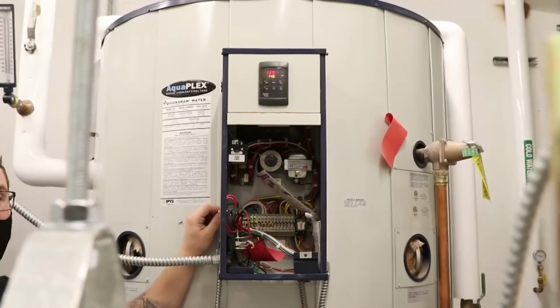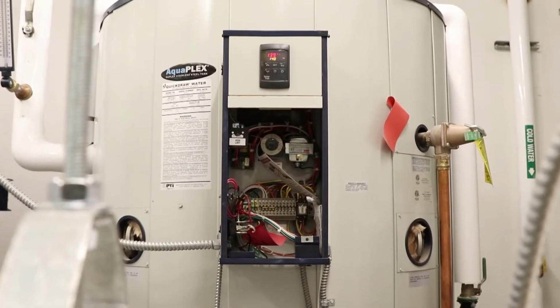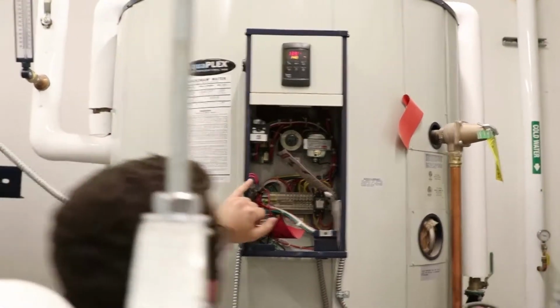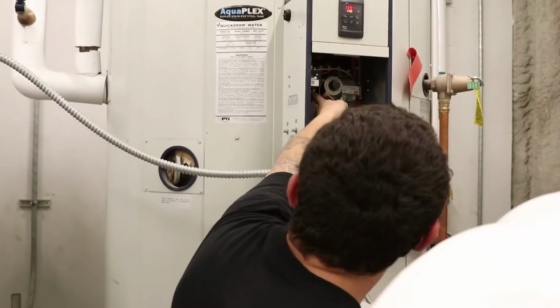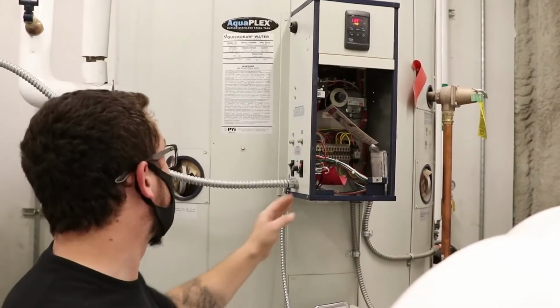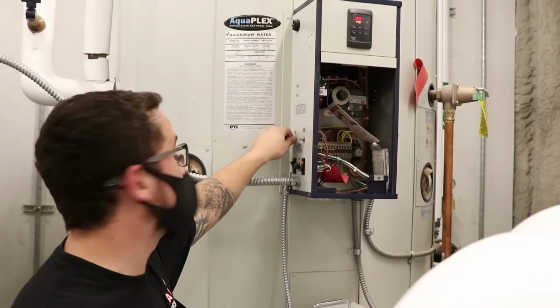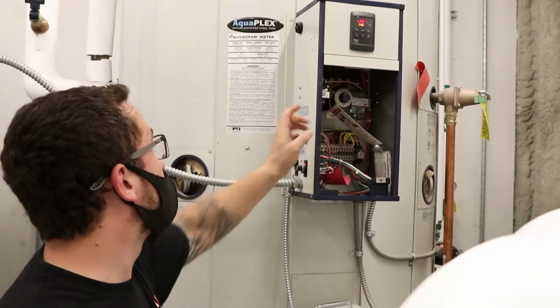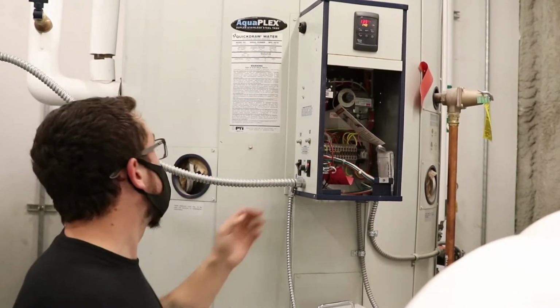As you can see, now you're in a low water condition where the water heater will not operate, to prevent a dry fire or damage to the heat exchanger or anything else. So now my red LED light is not on in there, so now I've confirmed that this low water cutoff does function and that it does stop operation of the water heater as it should.